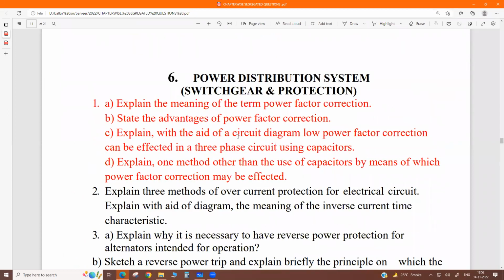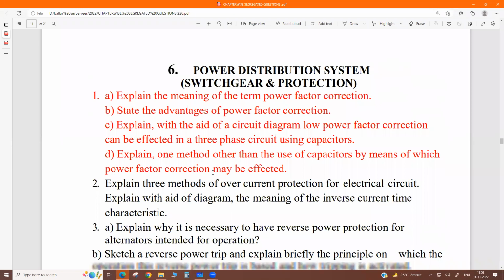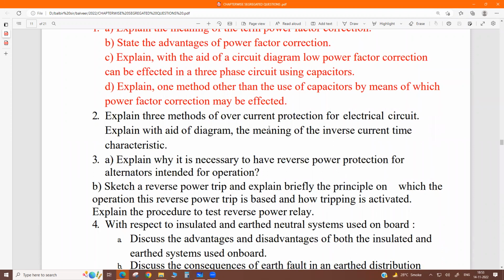Power distribution related questions here in ETO already, which are asked in your examination. That is, explain the meaning of the term power factor. So yesterday we discussed this, and the advantage of power factor correction means why we improve the power factor. So if power factor is high, losses are reduced, efficiency is improved, voltage profile is also improved. Explain with a diagram how we improve the power factor in three phase using a capacitor. So you have to show the three phase R Y B connected to load, and you put a capacitor bank, either star connected or delta connected. Okay. And other methods are synchronous condenser or automatic power factor correction panel. Explain the three methods of overcurrent protection. Here also it is there.